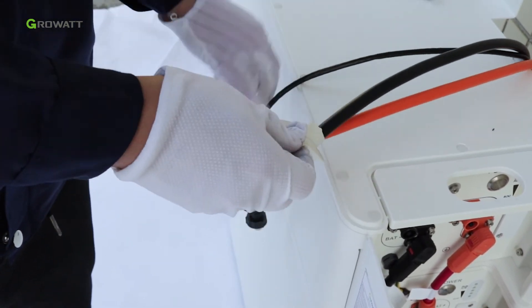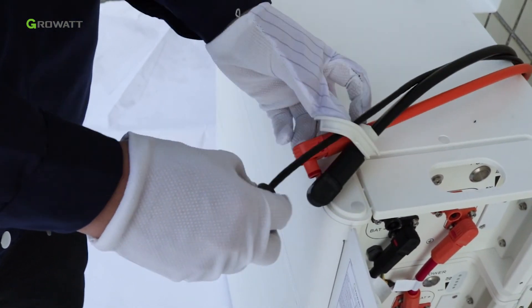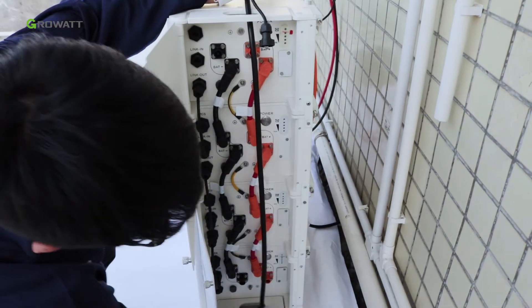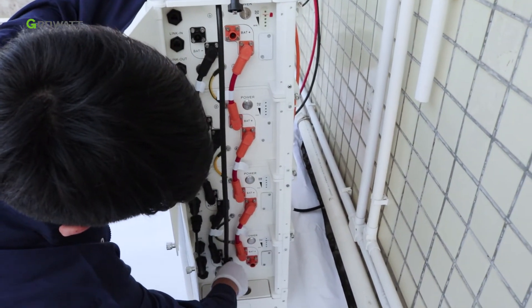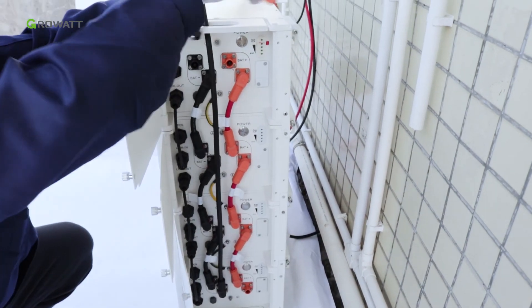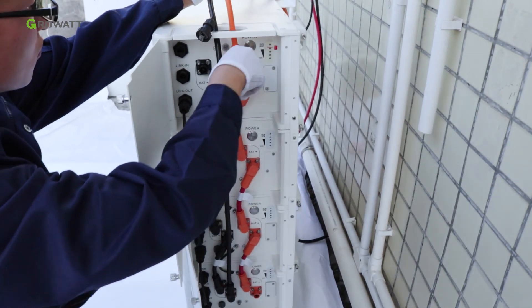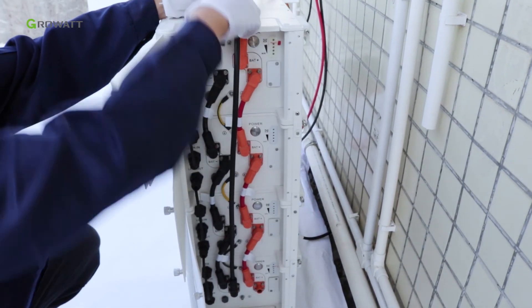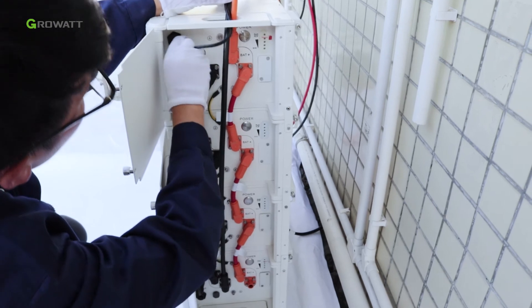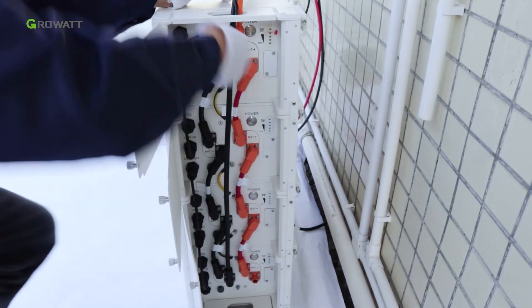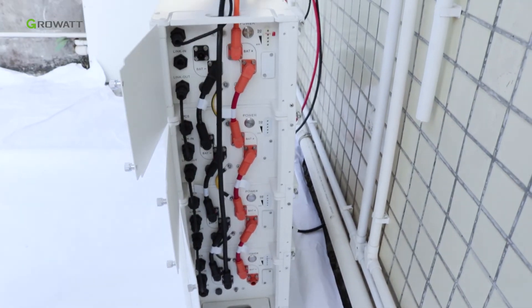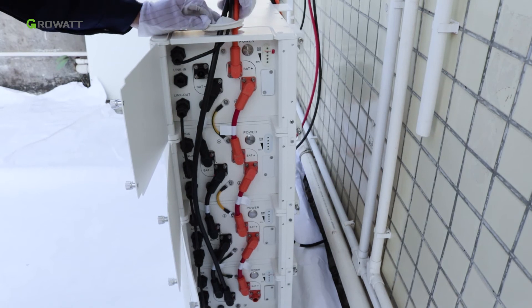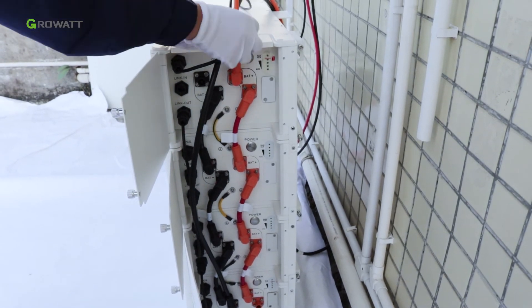Connect the negative power cable to the BAT minus port of the bottom battery pack. Connect the positive power cable to the BAT plus port of the top battery pack. Connect the communication cable to the PCS port of the top battery pack. Finally, put the rubber cover to the partial top cover.